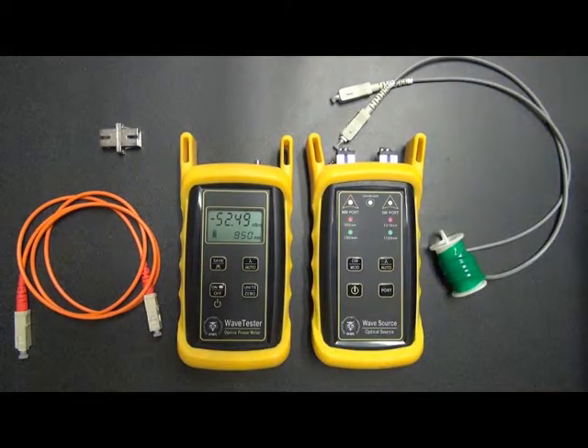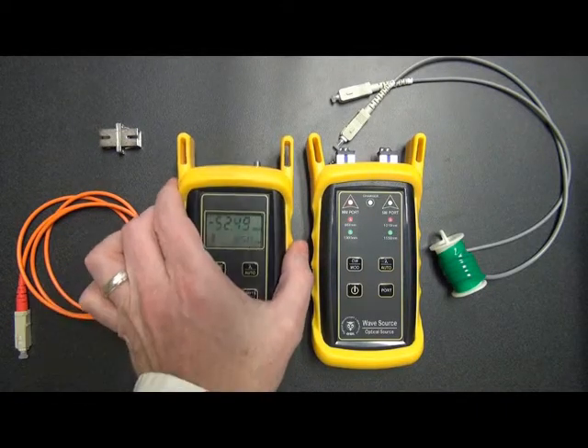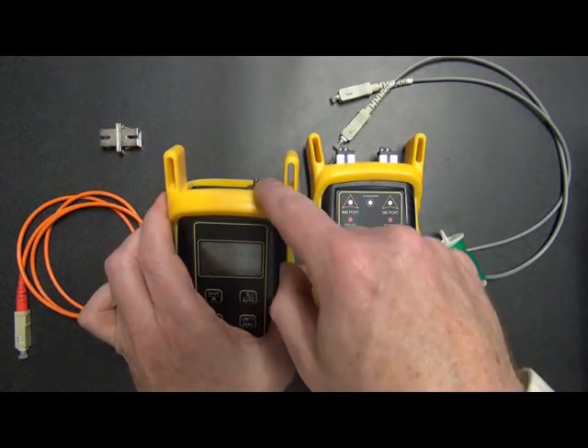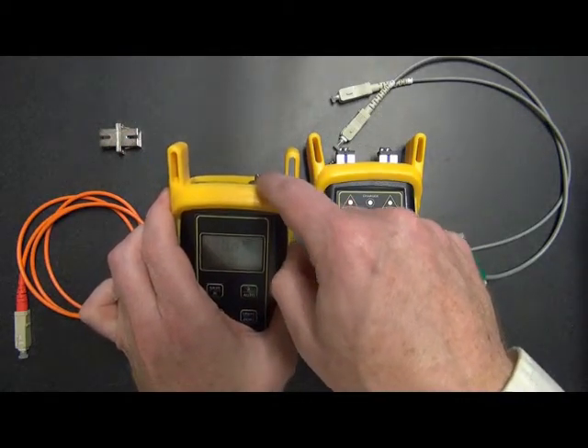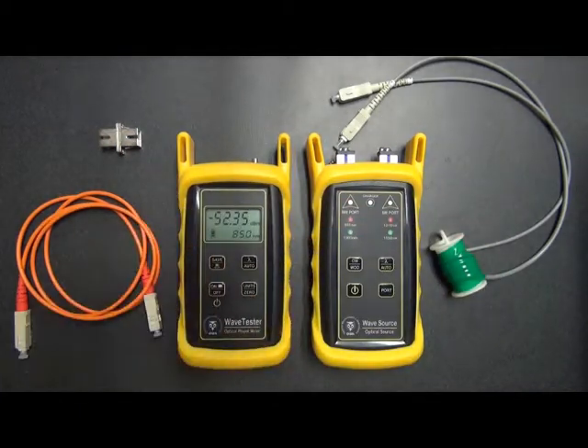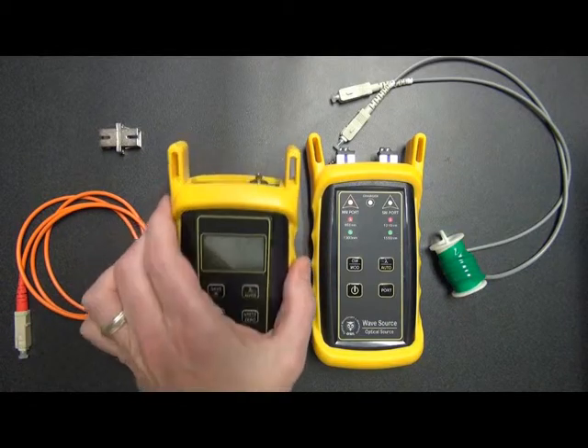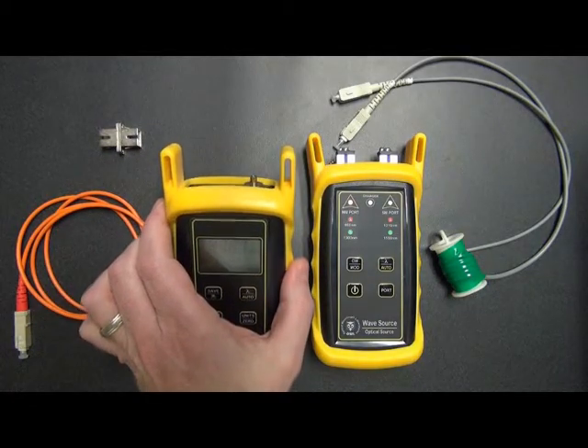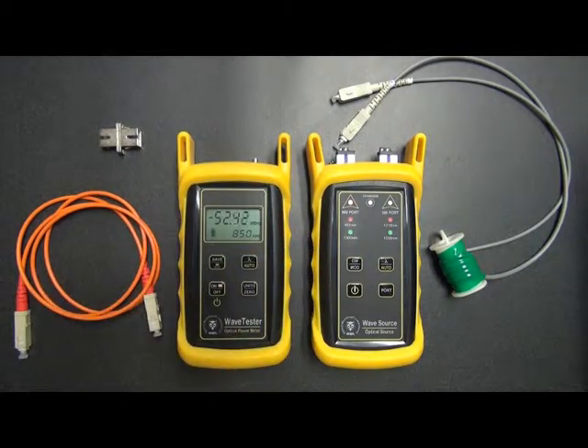However, this reading is a very low power reading, and what this means is we're measuring ambient room light. Obviously, there's no connector plugged in here, so it's measuring something. It's measuring ambient room light. This is a typical power level for ambient room light. So whenever you disconnect your fibers and have the detector port open like this, just remember that the reading you're getting is ambient room light.